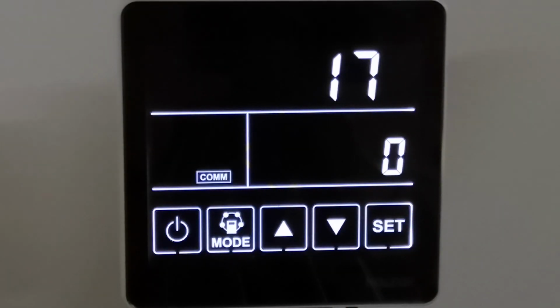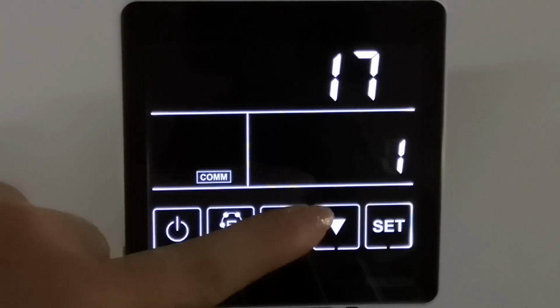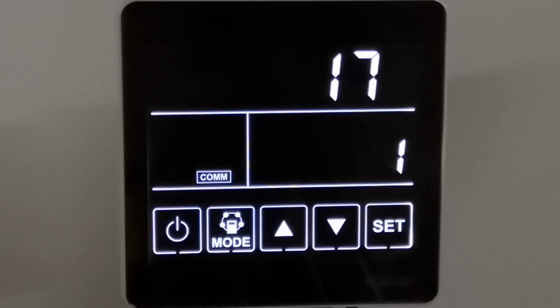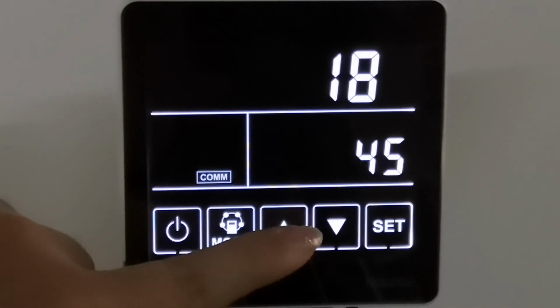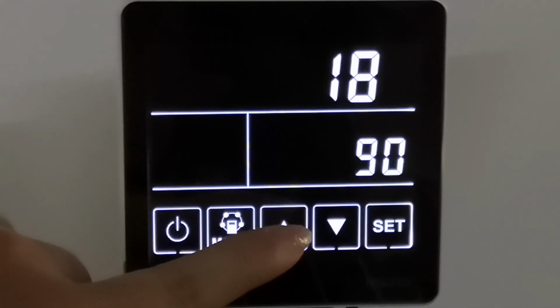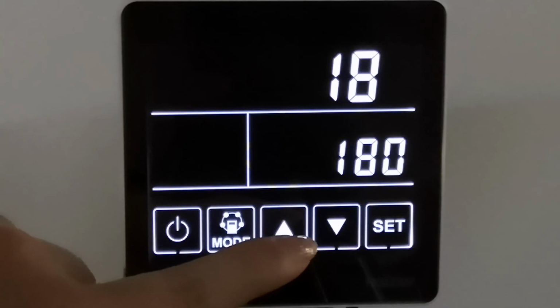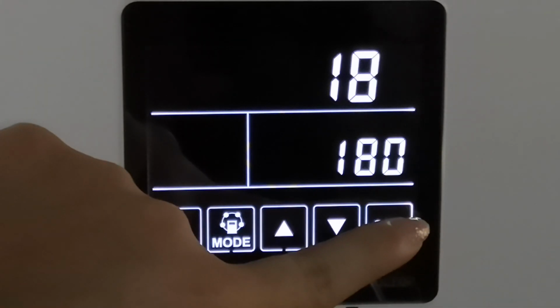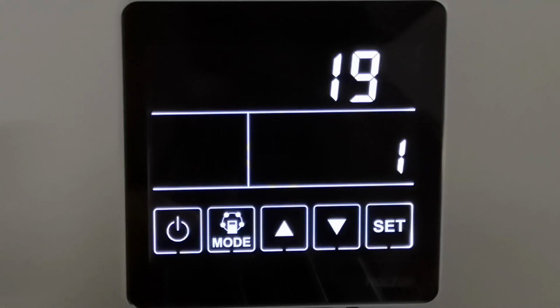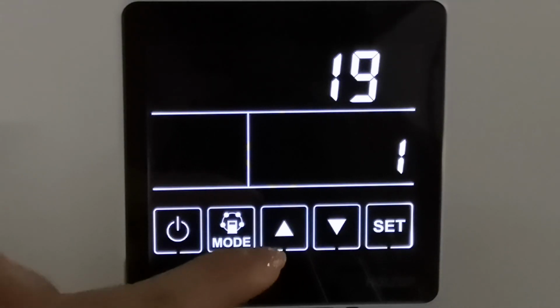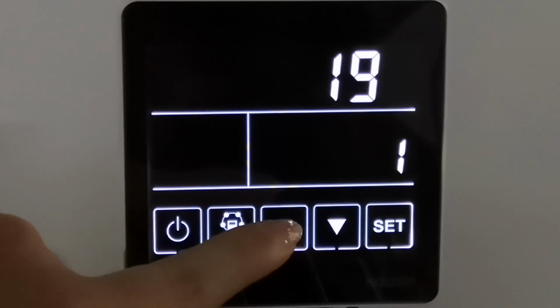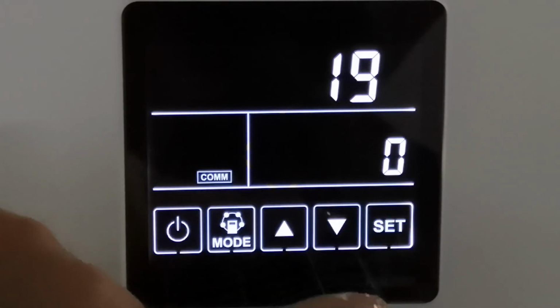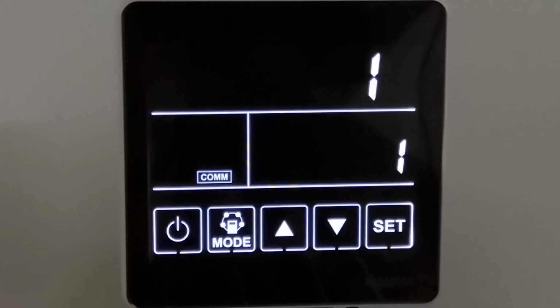Parameter 17 refers to the filter alarm. 0 means unavailable, and 1 is to clear the filter alarm and recount the time. Parameter 18 refers to the filter alarm setting. You can choose from 45 days, 60 days, 90 days, and 180 days. Parameter 19 refers to the differential pressure switch function. 0 stands for invalid, 1 stands for valid. The default value is 0. Finally, if you want to restore the factory settings, just press the up and down buttons simultaneously for more than 5 seconds. The parameters will be back to original.